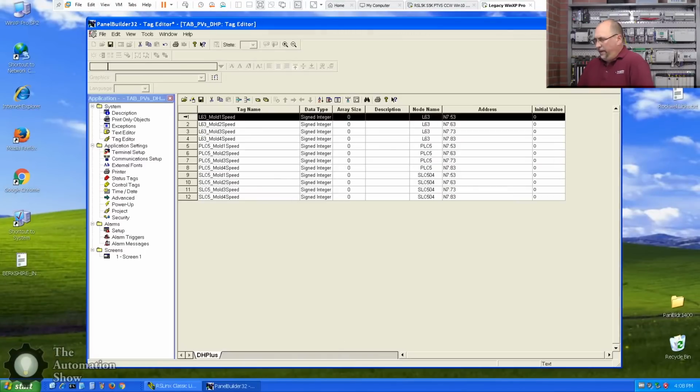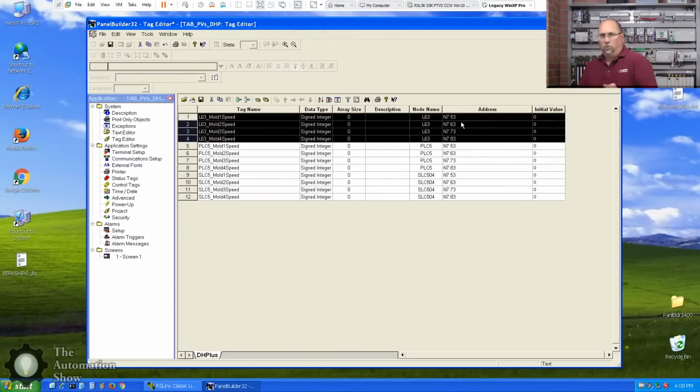Okay, and now the addresses we have here are incorrect because first of all, they need to be N27. That's where I mapped the MicroLogix 1400 data to, N27. And then it's going to start at 0, 0 through 49, not 50 through 99, because when I read in 50 through 99, I put them in that array at the beginning.